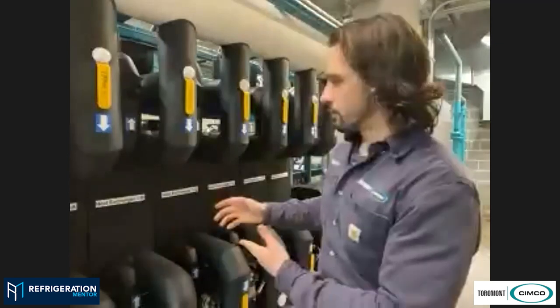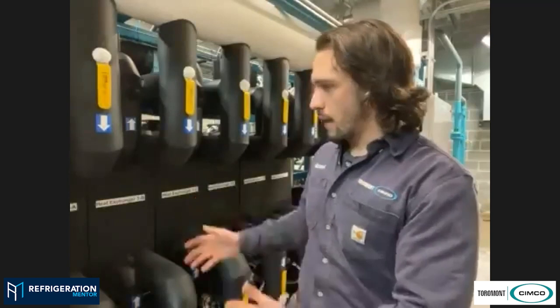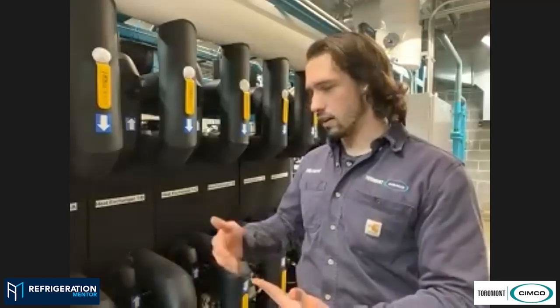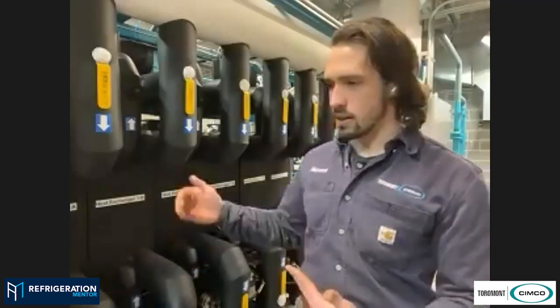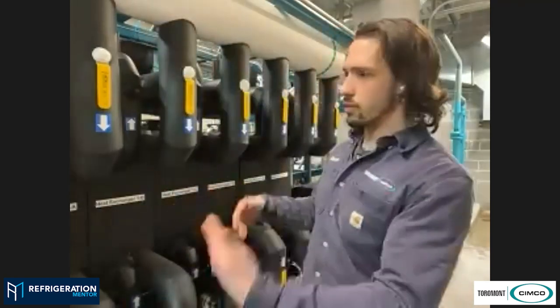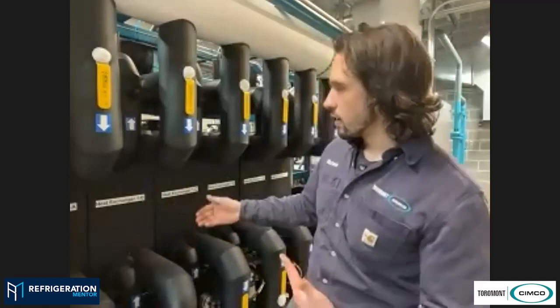That's super cool. So when the package initially starts up, the VFD compressor will run, and there's about a 5-minute delay between when that one starts and when we have confirmation of run and when the next compressor will start. That VFD compressor initially starting allows the system to stabilize before we bring on more load and start refrigerating. Once the additional compressors come on, based on a runtime rotation, compressor number one, which is on the VFD, starts acting as a trim to maintain stable suction pressure.